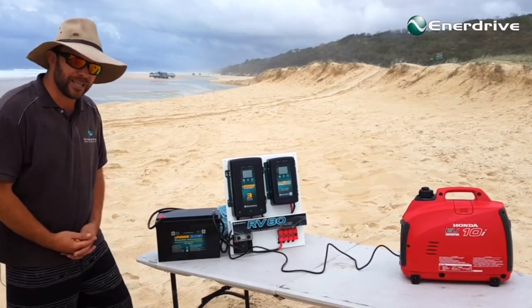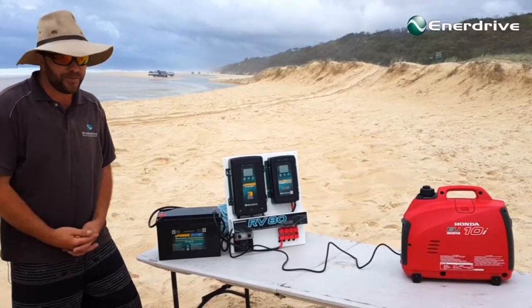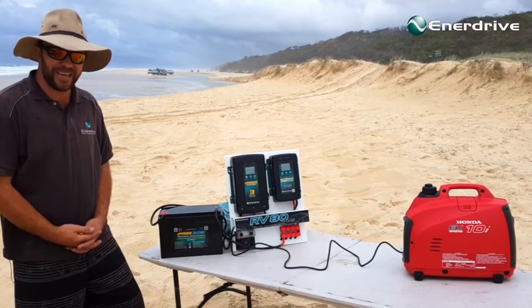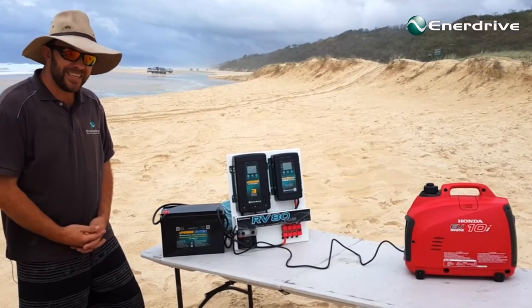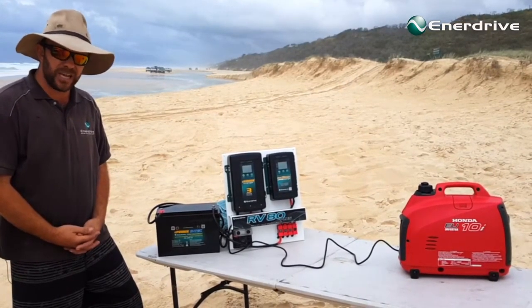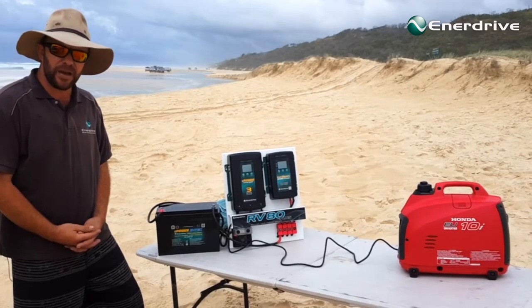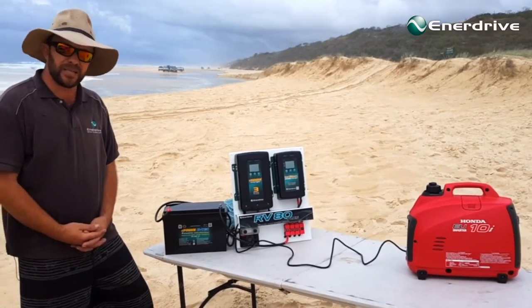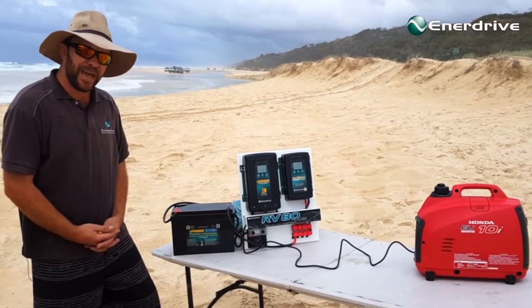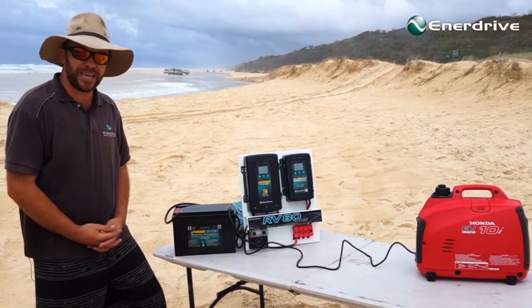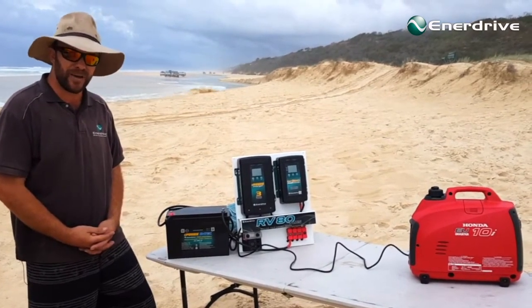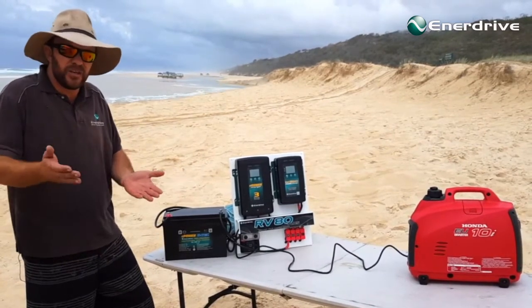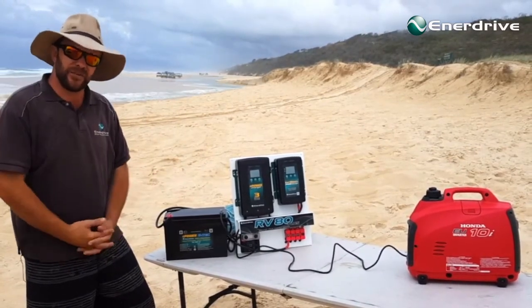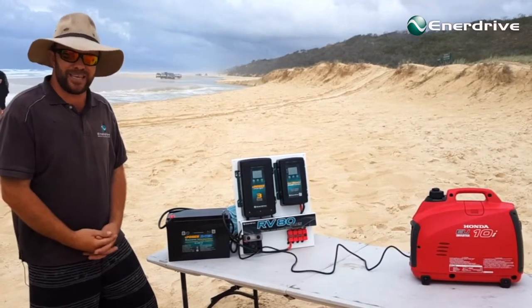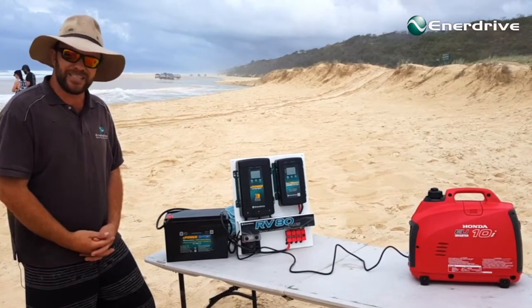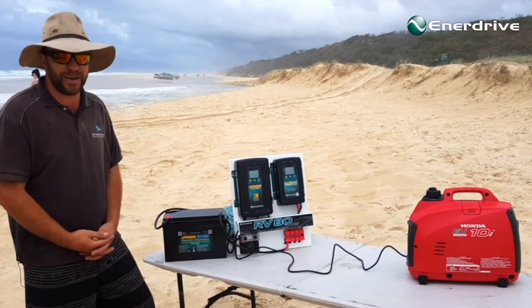Some of you may ask, when on earth would you need to do that? Well, there's lots of guys out there, particularly in the marine sector, with huge demand for large output charging solutions. ePower have got that covered by paralleling two 60 amp chargers together, maximizing efficiency, or should I say redundancy. Should any component fail - it happens to the best of us - you won't lose 100% of your charging output. You've still got a 60 amp charger to keep the system alive until you get the problem rectified. You can't get much better than that.